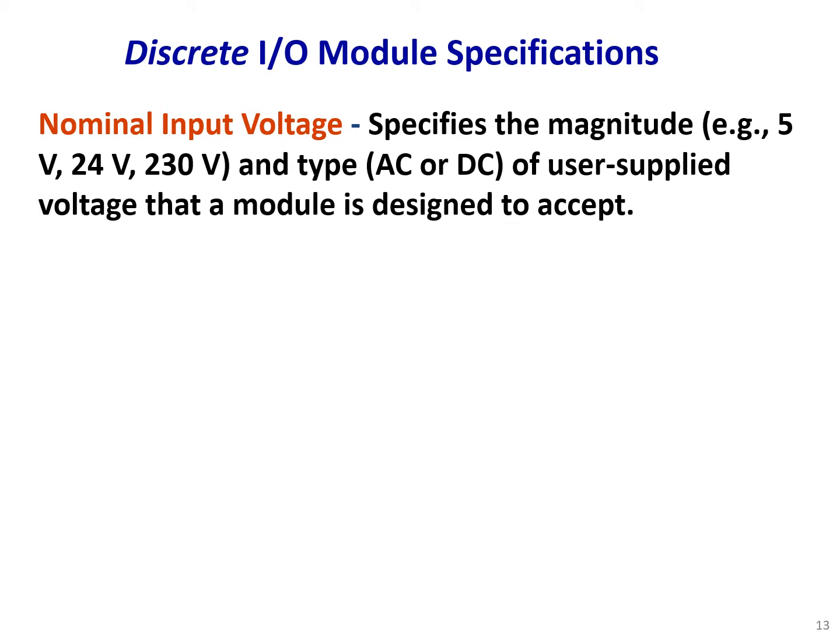I/O specifications — discrete I/O module specification. When we get any type of I/O module, it comes with a spec sheet that lists the specifications, and we want to familiarize ourselves with the most important ones. The first is nominal input voltage, which specifies the magnitude — for example, 5, 24, or 230 volts — and type, AC or DC, of the user supply voltage that a module is designed to accept.